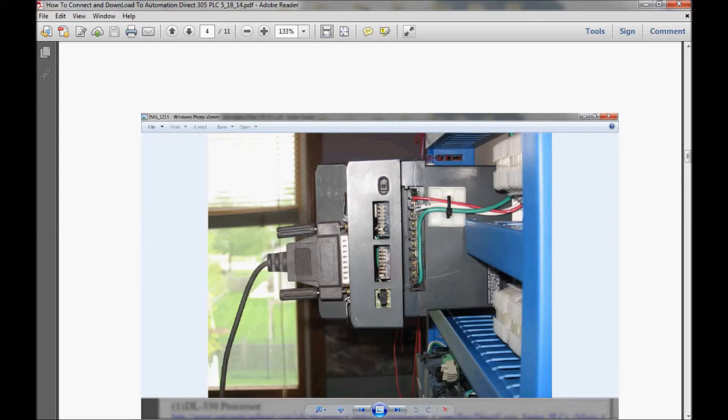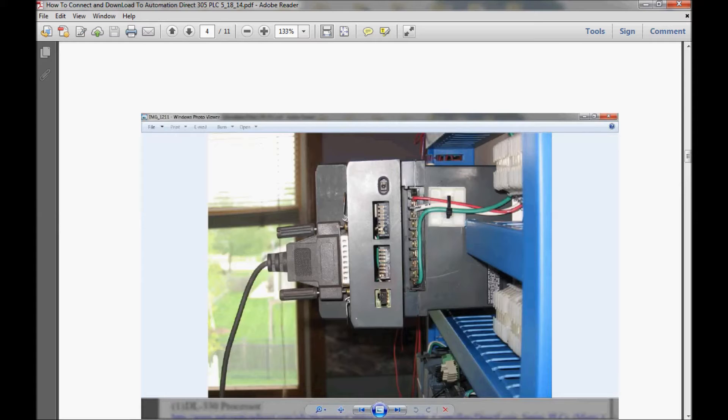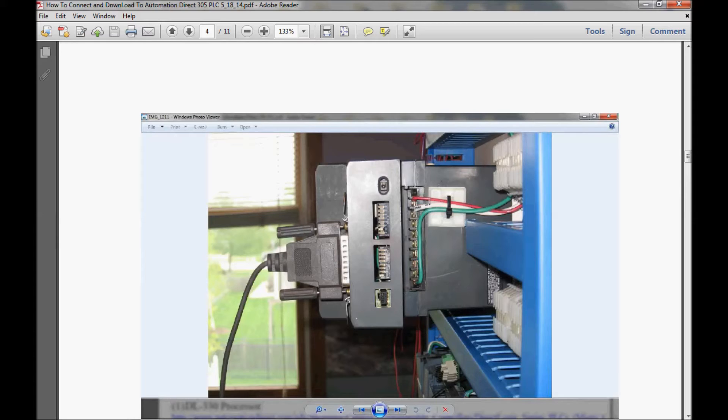Block number 2 here, just below that, is where the address is selected. The only DIP switch that I have in the on position there, which is to the left, is switch number 1. So that gives me an address of 1, and all the rest are selected to the right.